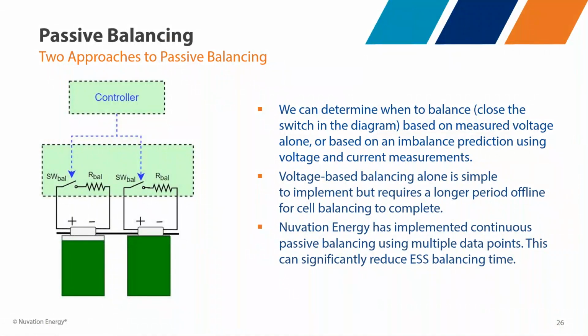In response to this, Nuvation has implemented in our Gen 5 battery management system what we call continuous passive balancing. This does an estimation of the unbalance in a system, and can continue balancing without requiring the system to be held at a high state of charge.